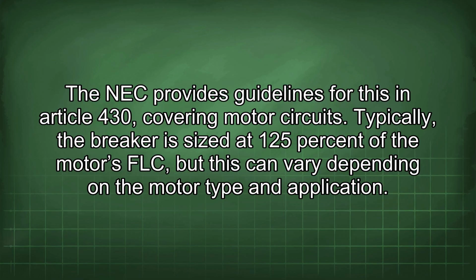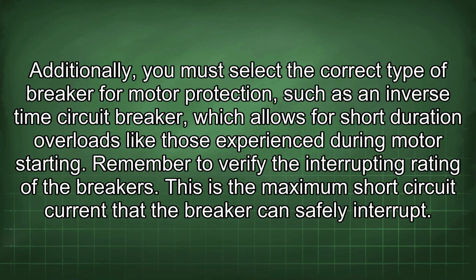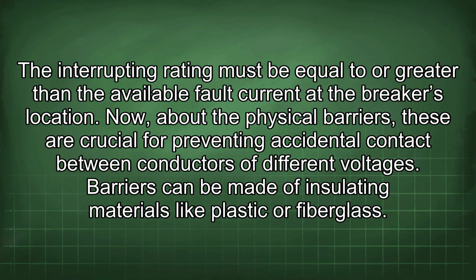Typically, the breaker is sized at 125% of the motor's FLC, but this can vary depending on the motor type and application. Additionally, you must select the correct type of breaker for motor protection, such as an inverse time circuit breaker, which allows for short duration overloads like those experienced during motor starting. Remember to verify the interrupting rating of the breakers. This is the maximum short circuit current that the breaker can safely interrupt. The interrupting rating must be equal to or greater than the available fault current at the breaker's location.